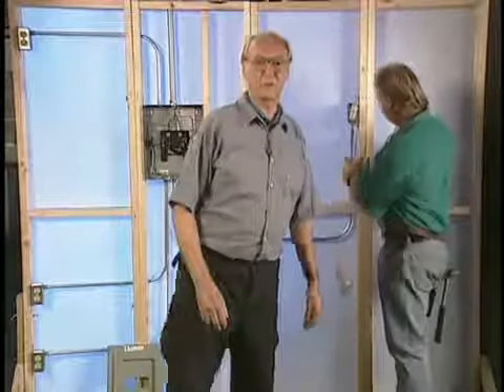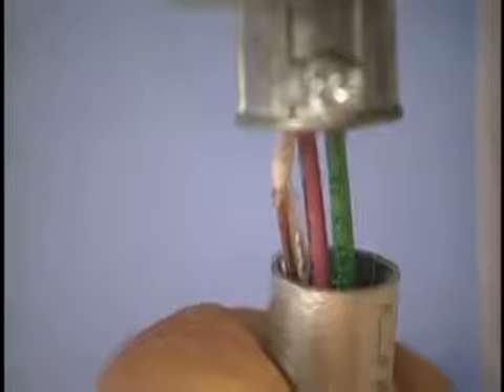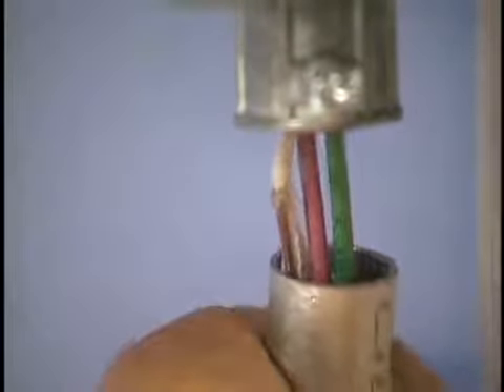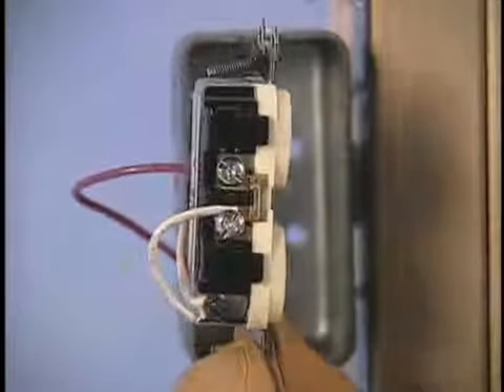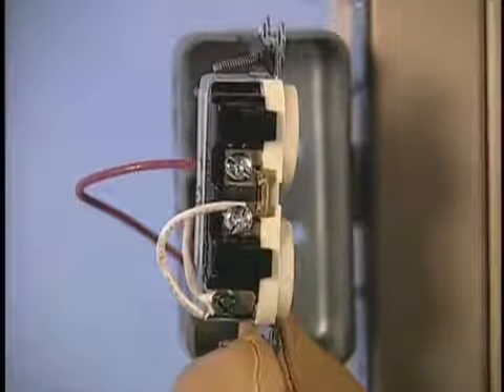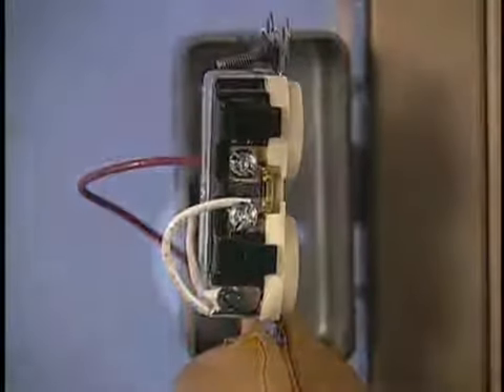Sometimes a neutral to ground error is found out in the circuit. Here is an example of such an error. The neutral is grounded because the neutral wire is nicked. Sometimes the sharp edges of a fluorescent light fixture mounted without the correct bushings will cut through the neutral insulation. And a third situation involves an intentional neutral connection to a grounding conductor. This happens for various reasons.